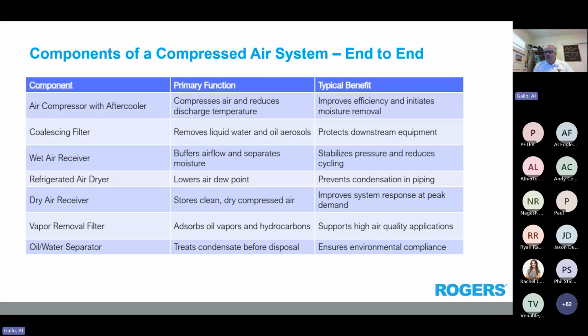We have coalescing filters, particulate filters, general purpose filters that will start removing more and more of the liquids, the aerosols, any debris that may be in there, organic material. Send it to a wet receiver. Some systems have a wet receiver before it actually goes to a dryer, refrigerated or a desiccant dryer. That helps buffer air. If you have a reciprocating air compressor, because it bounces around so much, we may get surges within the system. So we want a wet air receiver to help with that.